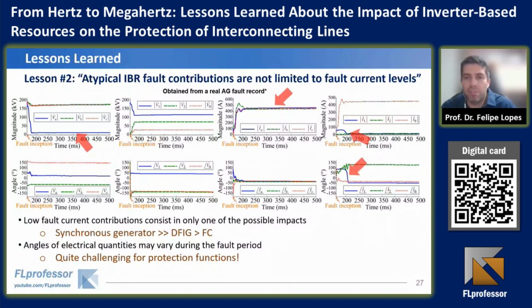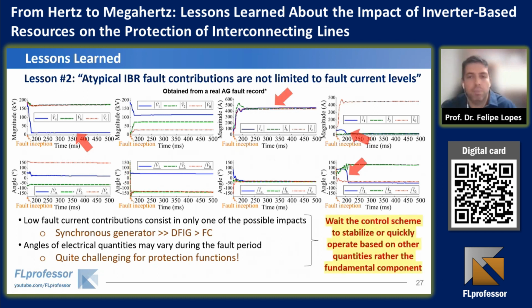But there is a very interesting behavior here that can be noted, because low fault current contributions are only one of the possible impacts. We know that. But we noticed that in this real case, the angles were changing for some time, and then they stabilize. So it's difficult to take a decision here because the control scheme is still converging to its final values. And we could face, for the first time, the need to wait for the control scheme to stabilize.